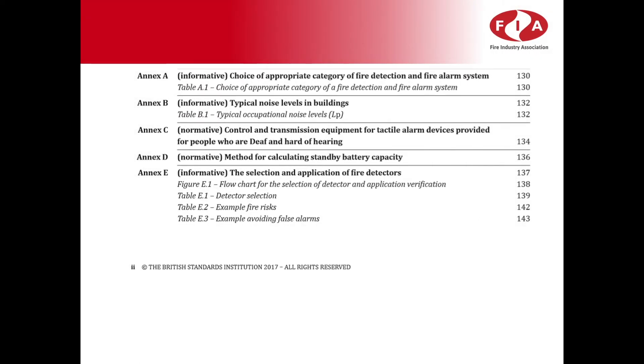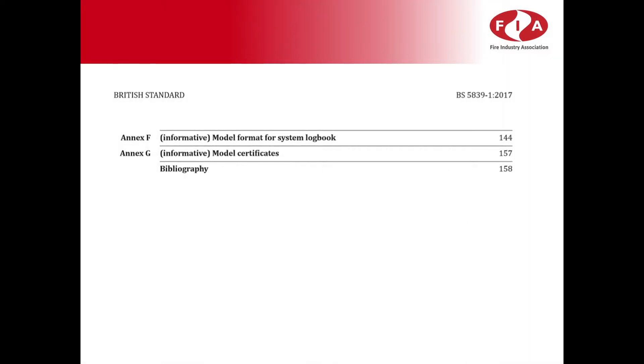The final part of the Code of Practice details annexes A through to G. Annex A provides information on the choice of appropriate category of fire detection and fire alarm system. Annex B details information relating to the typical noise levels within buildings. Annex C relates to the control and transmission equipment for tactile alarm devices provided for people who are deaf and hard of hearing. Annex D details the method for calculating the standby battery capacity. Annex E relates to the selection and application of fire detectors. Annex F provides detailed information on the format for the system logbook, and Annex G details information relating to the model certificates.